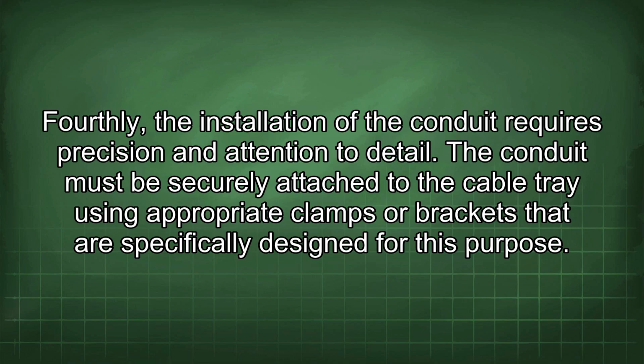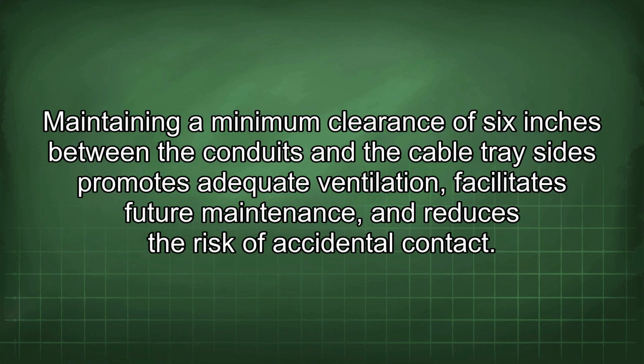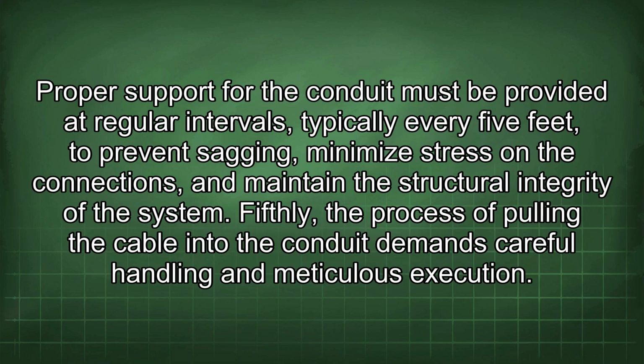Fourthly, the installation of the conduit requires precision and attention to detail. The conduit must be securely attached to the cable tray using appropriate clamps or brackets that are specifically designed for this purpose. Maintaining a minimum clearance of 6 inches between the conduits and the cable tray sides promotes adequate ventilation, facilitates future maintenance, and reduces the risk of accidental contact. Proper support for the conduit must be provided at regular intervals, typically every 5 feet, to prevent sagging, minimize stress on the connections, and maintain the structural integrity of the system.